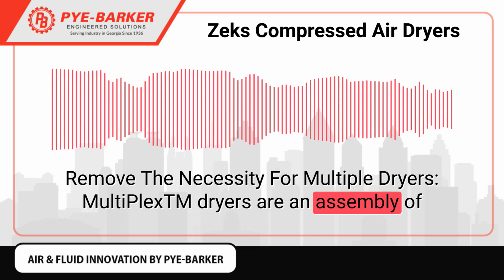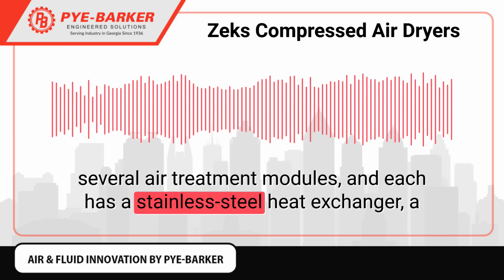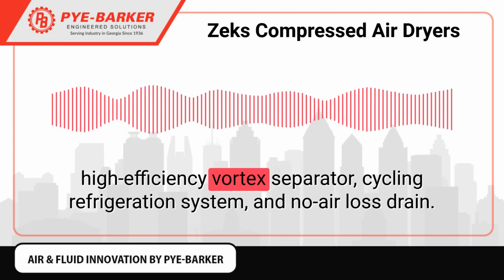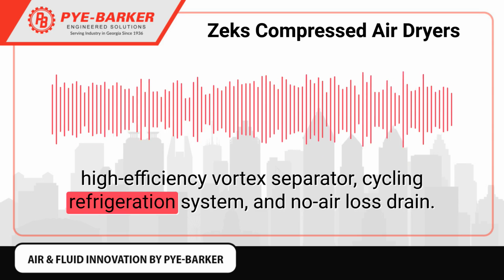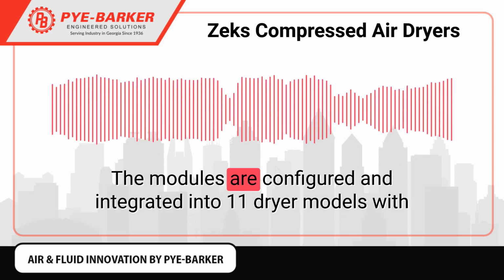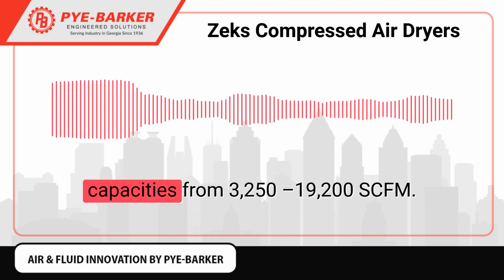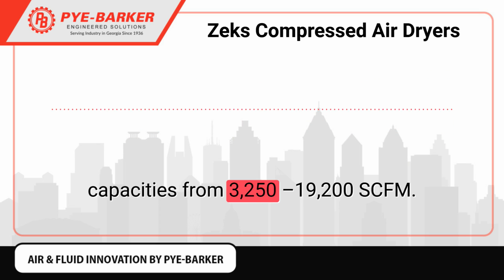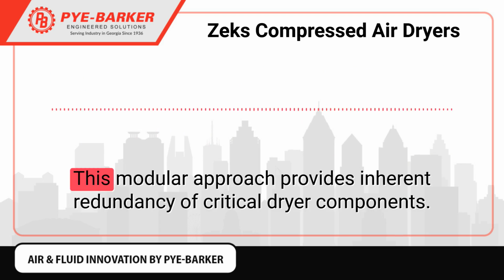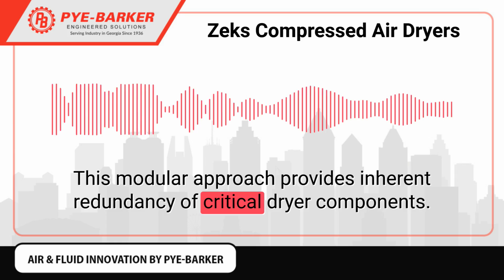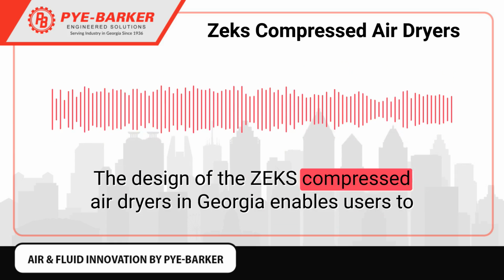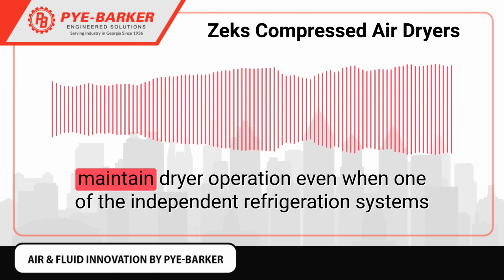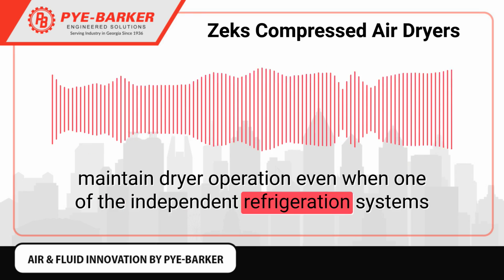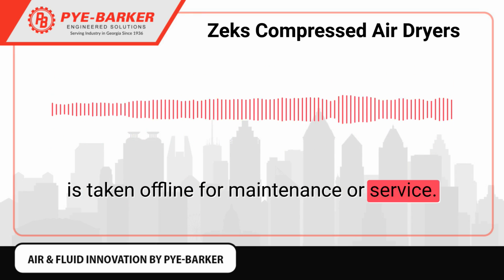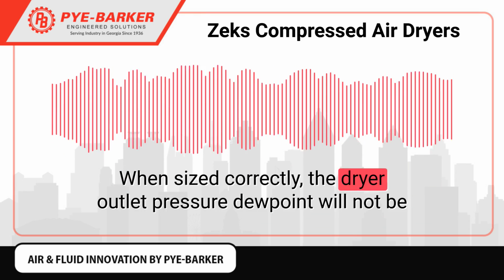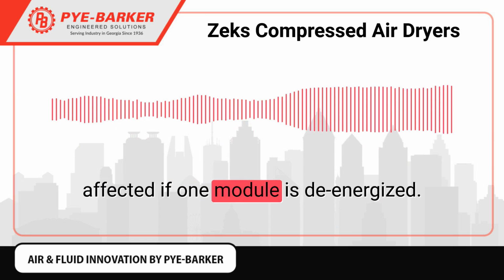MultiPlex dryers are an assembly of several air treatment modules, and each has a stainless steel heat exchanger, a high-efficiency vortex separator, cycling refrigeration system, and no air loss drain. The modules are configured and integrated into 11 dryer models with capacities from 3,250 to 19,200 SCFM. This modular approach provides inherent redundancy of critical dryer components. The design of the Zeks compressed air dryers in Georgia enables users to maintain dryer operation even when one of the independent refrigeration systems is taken offline for maintenance or service. When sized correctly, the dryer outlet pressure dew point will not be affected if one module is de-energized.